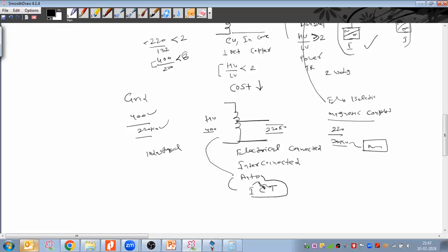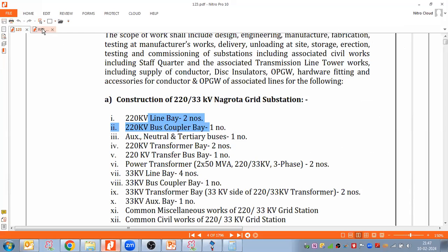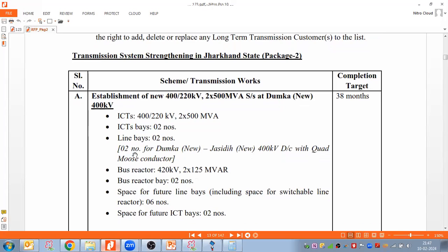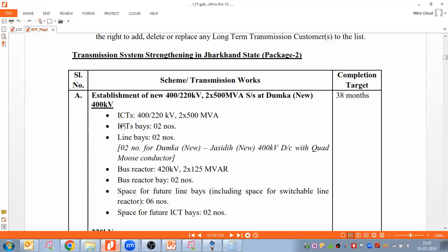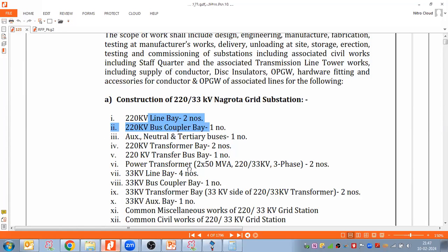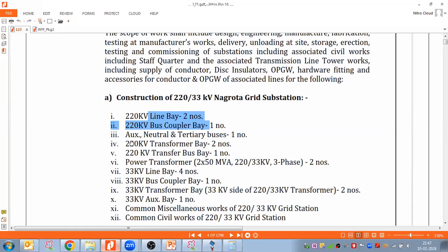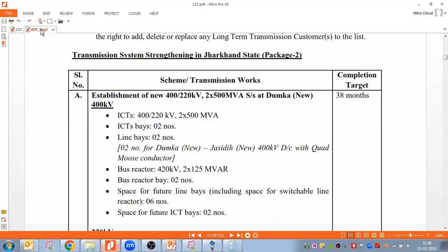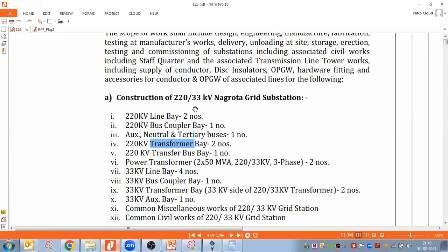So here, if you see in this particular scope of the work, this is the 400 kV by 220 kV. I'm going to use the auto transformer. Auto transformer is electrically interconnected. Due to this reason, in this scope of the work, the word ICT is written. In this scope of the work, the 220 kV and 33 kV are electrically isolated, and I'm using a simple two winding type power transformer. So due to that reason, here the words power transformer are written. Am I clear with the comparison between both scopes of work and the terminology for the transformer representations? Yes, sir.